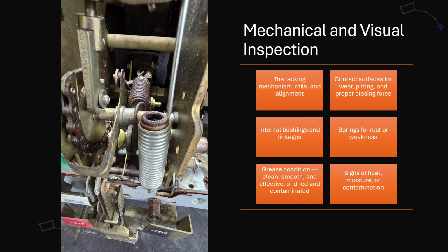After all electrical tests are complete, we physically examine the breaker, because even the best readings can't detect mechanical failure. Breakers are complex machines. Springs fatigue, bearings bind, lubrication dries up, and components fall out of adjustment. These issues slow response times or prevent operation entirely.